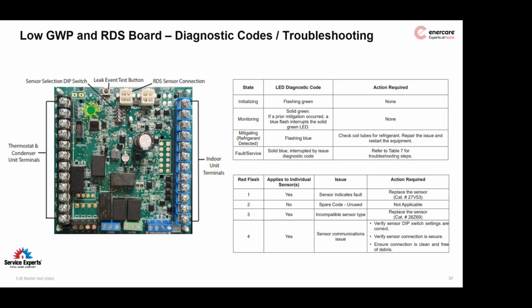Assuming that the fault has been corrected. Let's assume it's maybe the sensor's in the wrong port or something. Now, one thing we learned while we were in Ottawa, Bill and I were in Ottawa, talking to Ian from Lennox, is in the event, and again, this is very Lennox specific, so I want to make sure I'm saying this correctly. In the event the Lennox RDS sensor fails, it doesn't have a refrigerant leak, the sensor itself has failed. This may be more for the service folks. If the sensor has failed, or there is something wrong with the sensor specifically, this board will not lock out the customer's heating or cooling. It will just notify that the sensor has failed, that the sensor has to be replaced.